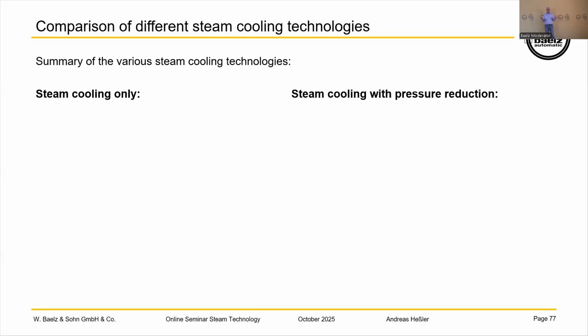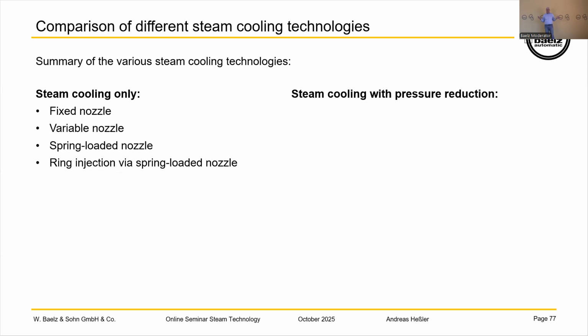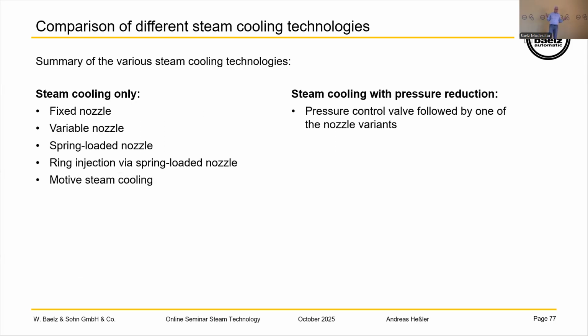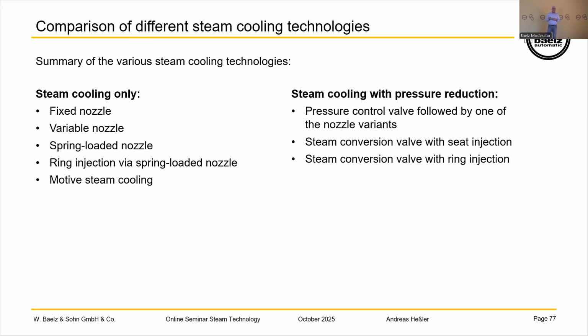Here is just a quick overview. When you have steam cooling only, you can use a fixed nozzle, variable nozzle, spring-loaded nozzle, ring injection via spring-loaded nozzle, or motive steam cooling. If you have cooling with pressure reduction, we have a pressure control valve followed by a nozzle system on the left side. You can have a steam converting valve with seat injection, a steam converting valve with ring injection, or a steam converting valve with a motive steam head.